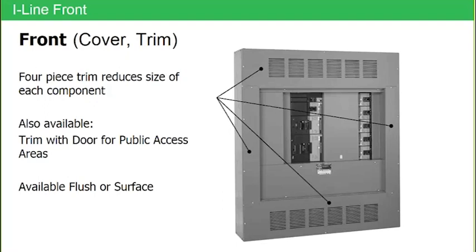Obviously the door is going to cover up all the breakers, as it says, for public access areas. So if this panel board is located in a public access area, obviously you would not want this particular cover because the breaker handles are exposed. But if this panel board is located in the basement of the building in the gear room, and that gear room is a locked gear room, then this particular cover would be perfectly fine.